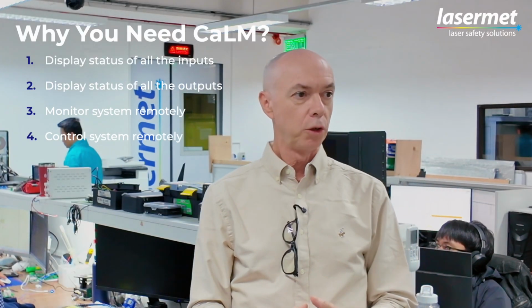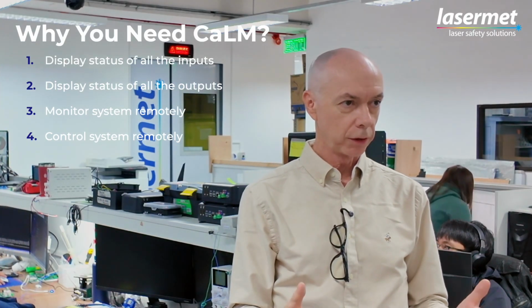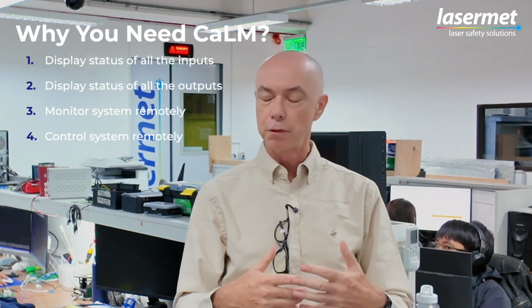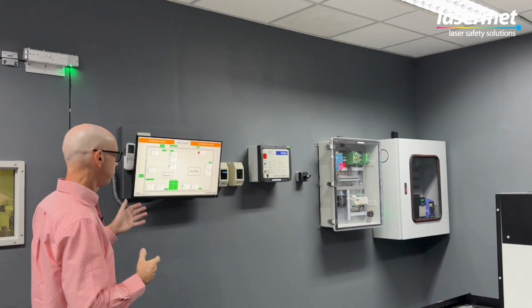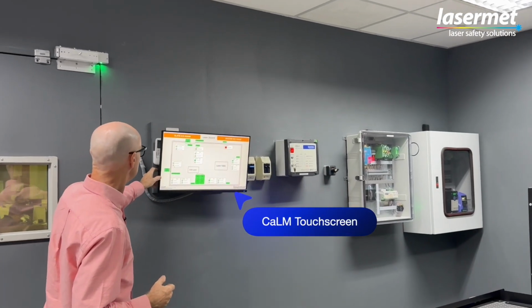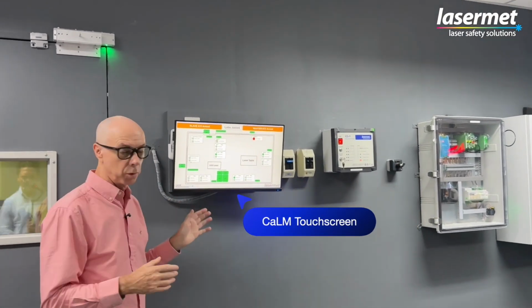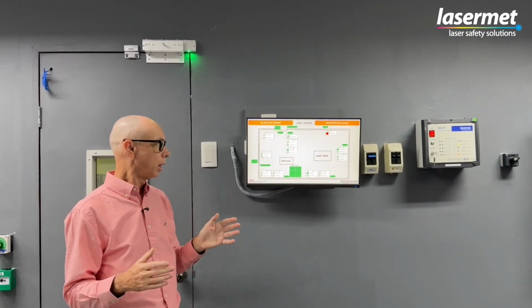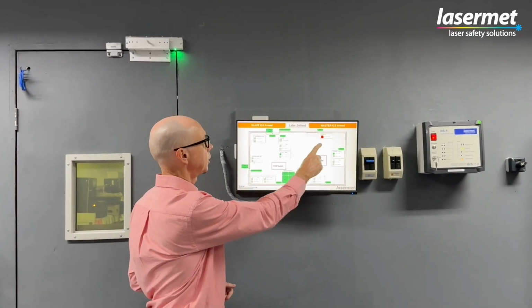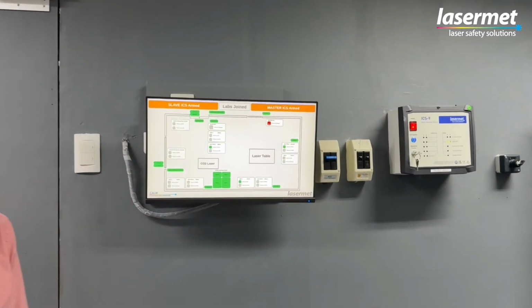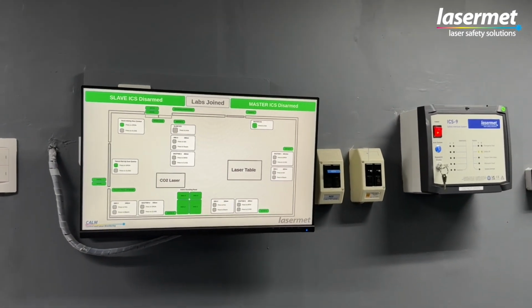Fourth reason would be remote control. So you can also control the status of the interlock system and aspects of the interlock system from a touch screen, and that could be a touch screen within the lab. It therefore gives you more possible points at which you could control the system within the lab. And that means arming the system, disarming the system, enabling a laser, disabling a laser, opening a shutter, closing a shutter. You could do that from a touchscreen inside the lab, or from a touchscreen in a control room that's outside the lab.